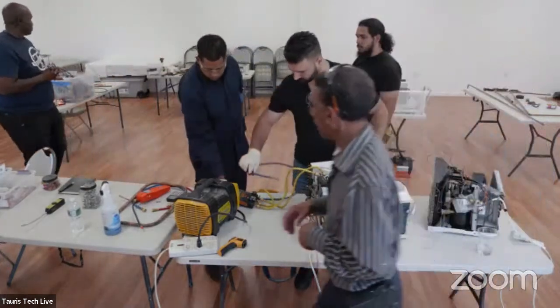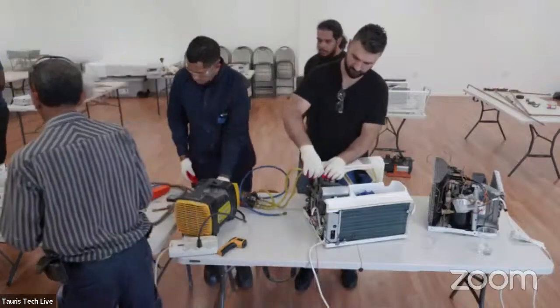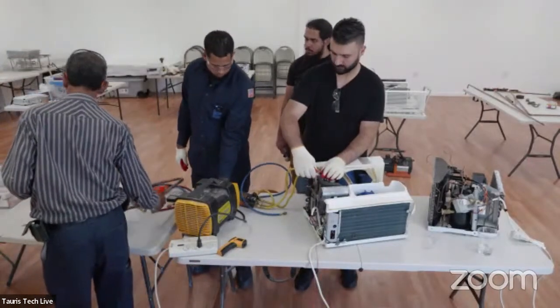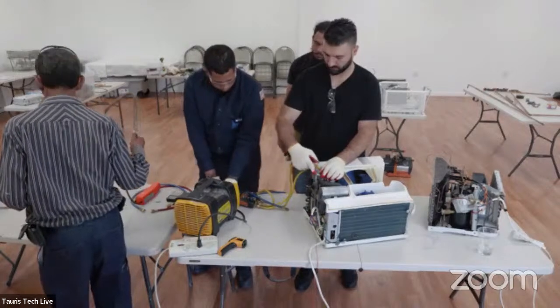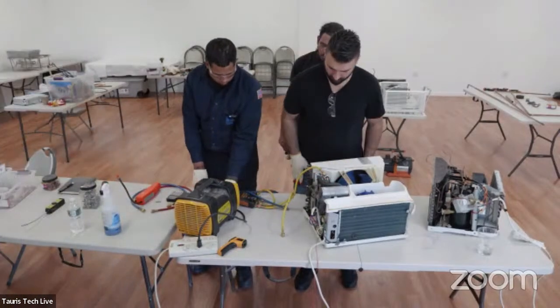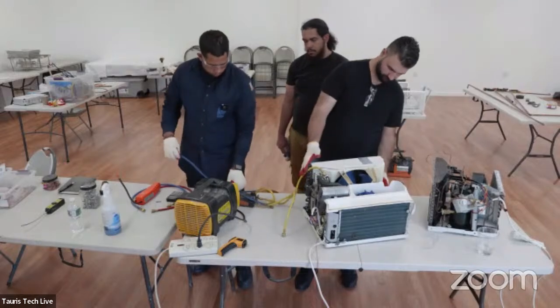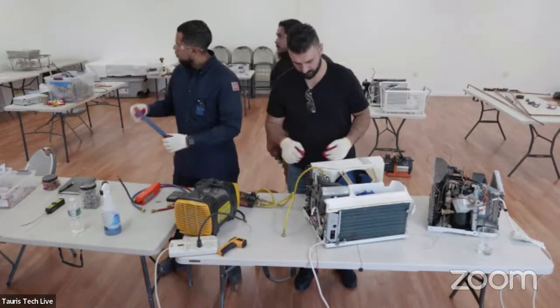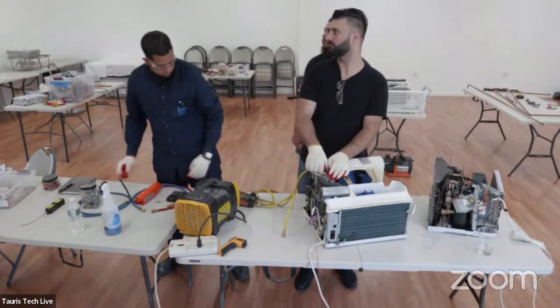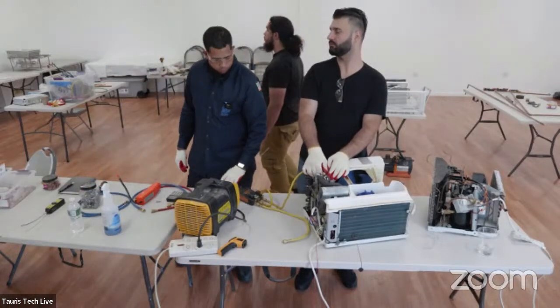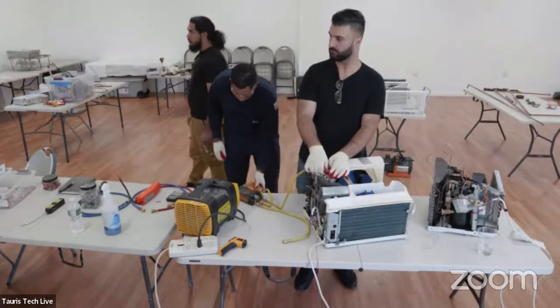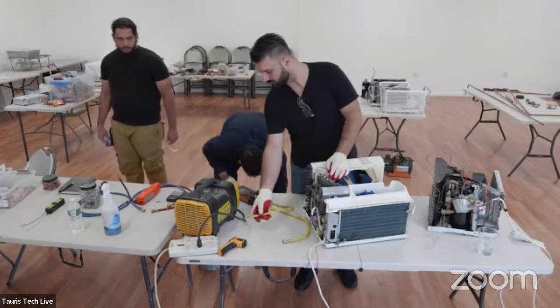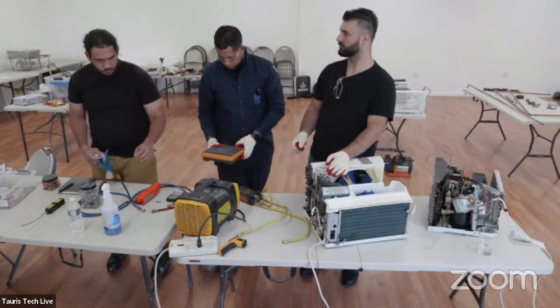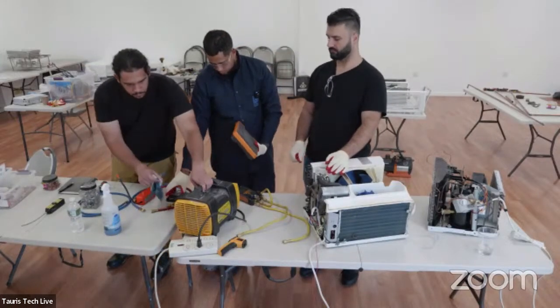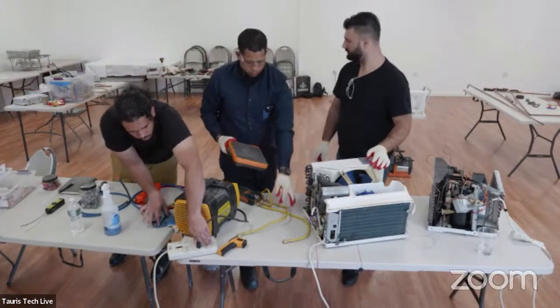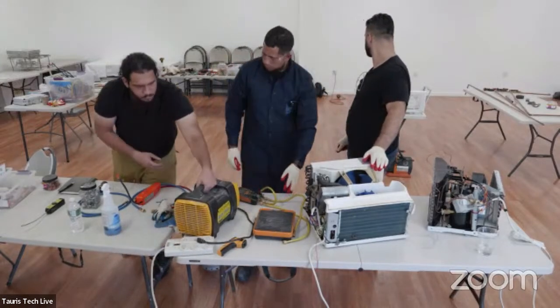So let's say you have a recovery machine that you're about to use for a job - is there refrigerant in there? Sometimes when I'm here and nobody's around, I might take one recovery machine and recover from that into a tank. But there's a first thing you've gotta do - check your pressure to make sure you know what kind of refrigerant's in there. Most of the time we're doing 410A, but you know, when we were going to that spot, it had R22.